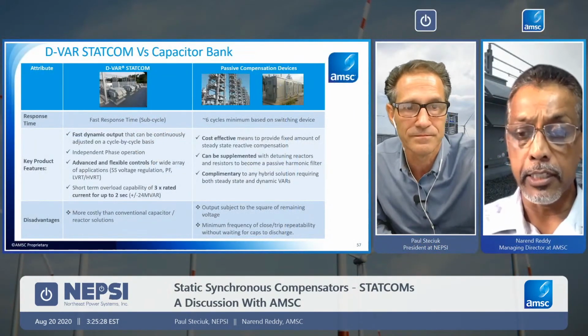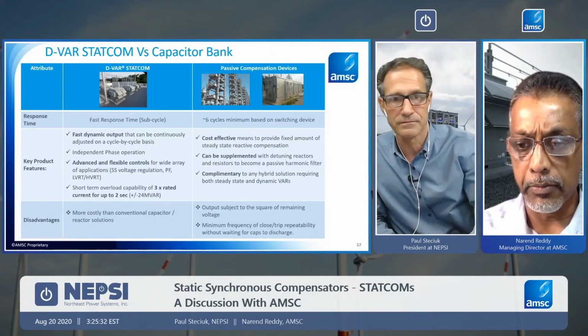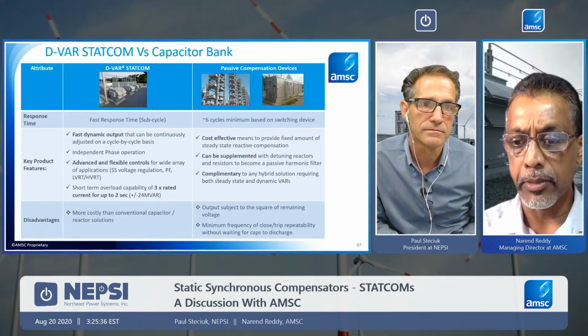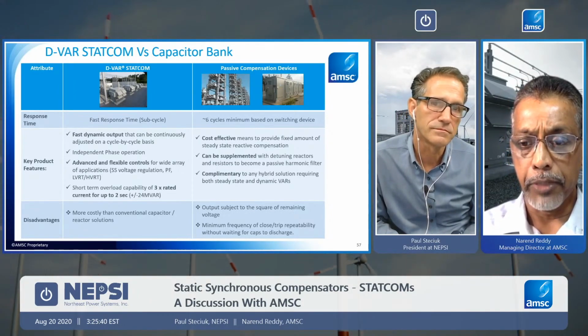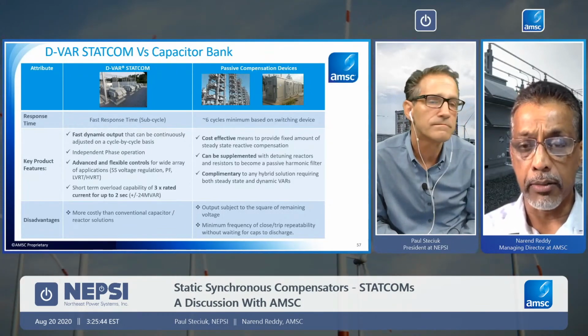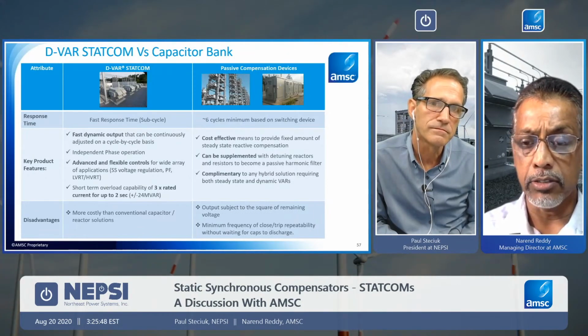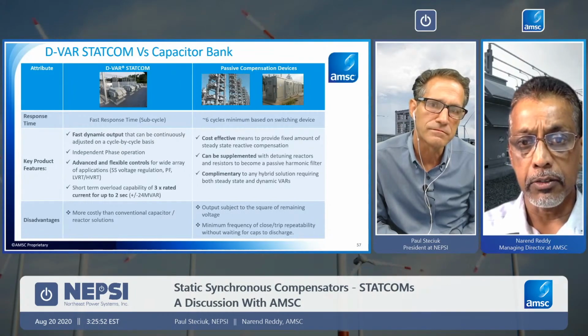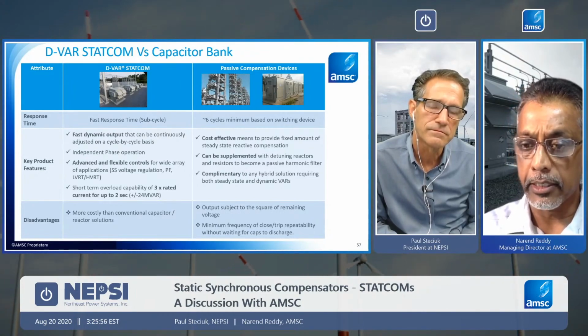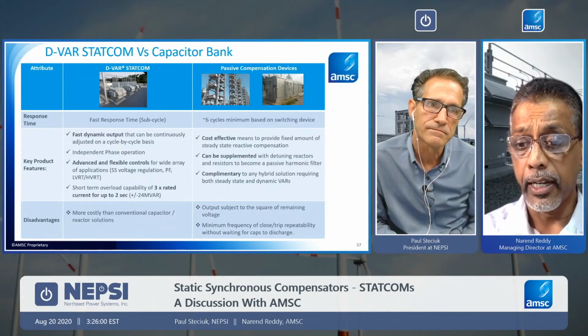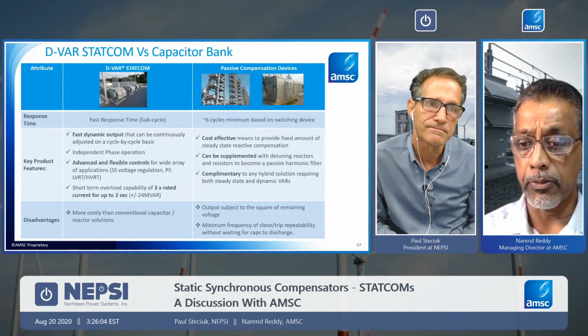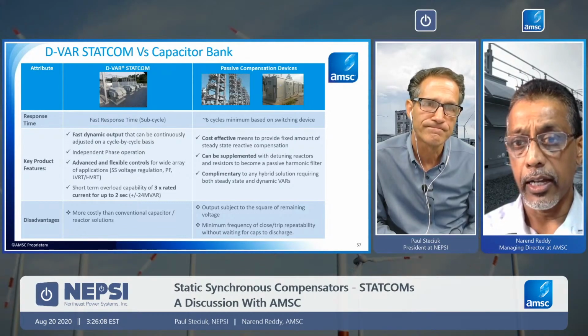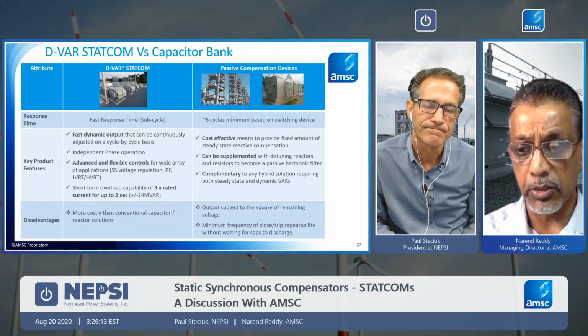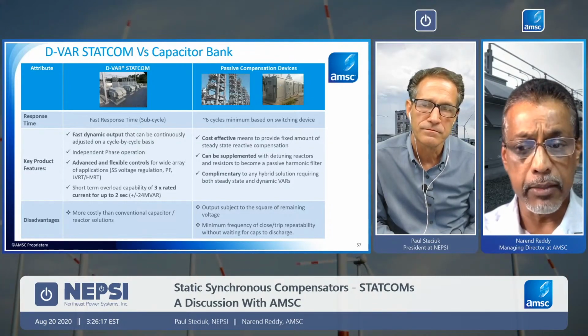Sure. So if I can advance the slide. Cost is a major factor in the decision, and in any solution. Depending on the customer, the application, and the appetite of the customer to solve the problem, what's important for us to understand here is really the application. As we mentioned earlier, both of these devices, a STATCOM unit as well as a passive capacitor bank, filter bank, or reactor bank, all provide reactive power. The question is they have their own place in terms of the value proposition they bring to the customer: speed of response, capability, how fast they are switched, and how best they can be used.